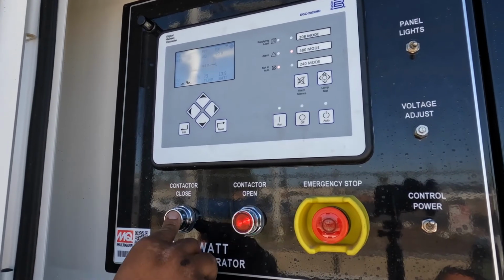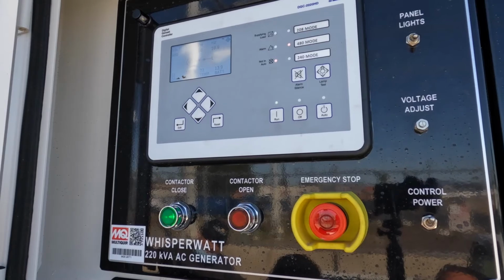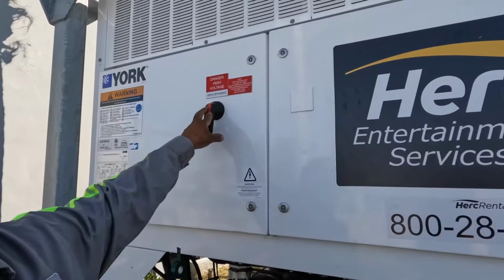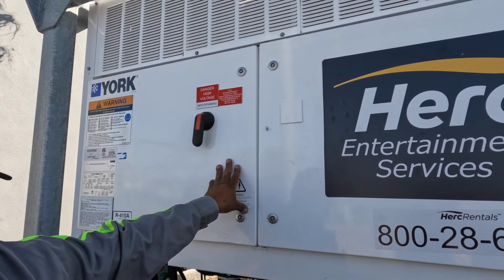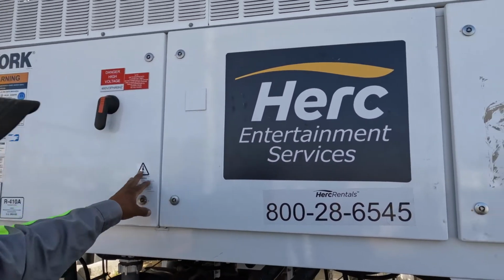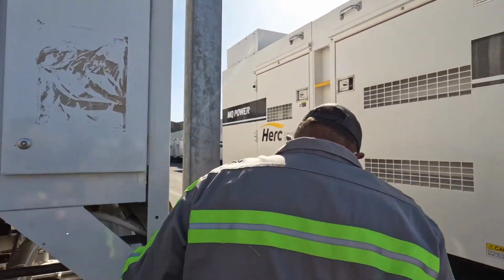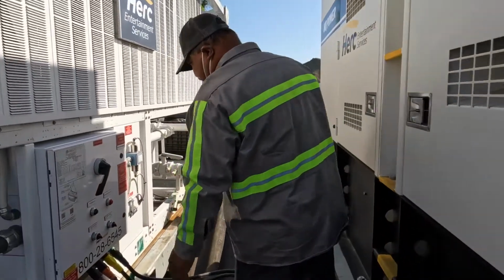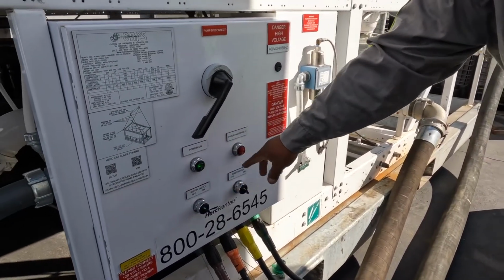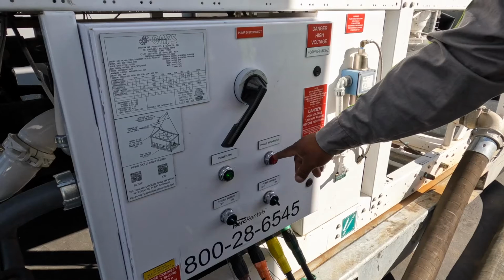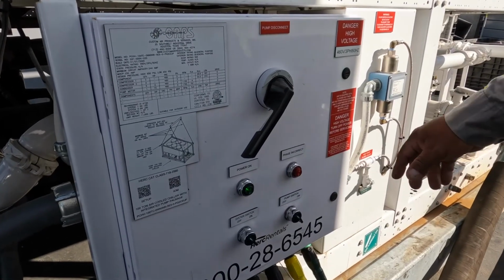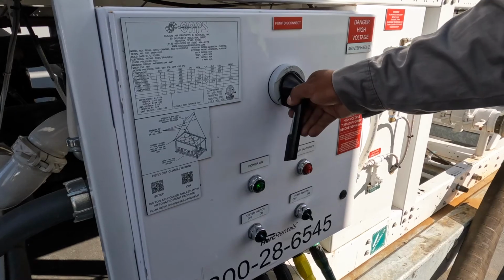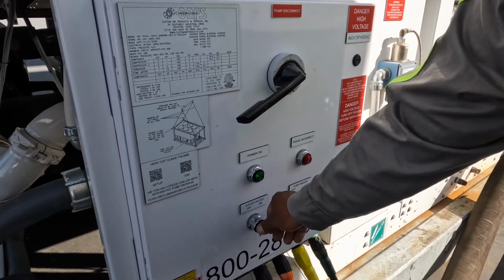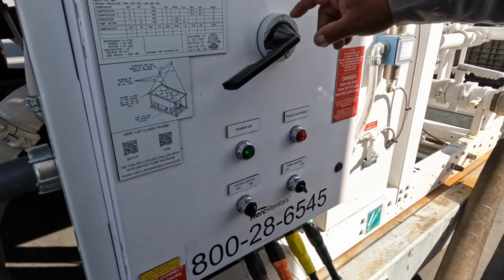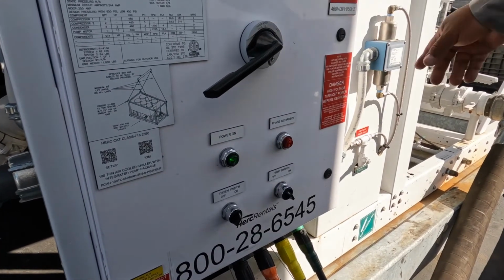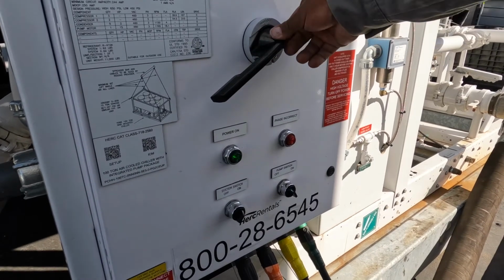The contactor closes, and that will send power to the chiller. So this is your main breaker for the chiller system. Make sure that's on. Then you come here. Make sure you have a green light, no red light. The red light must be off. However, when you first turn it on, you'll see this is the breaker for the pump as well as for the electronics on the chiller.